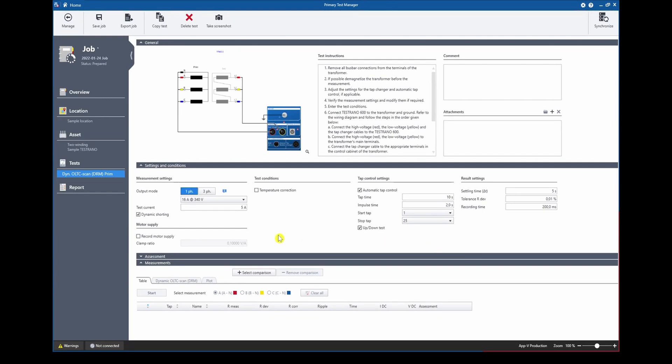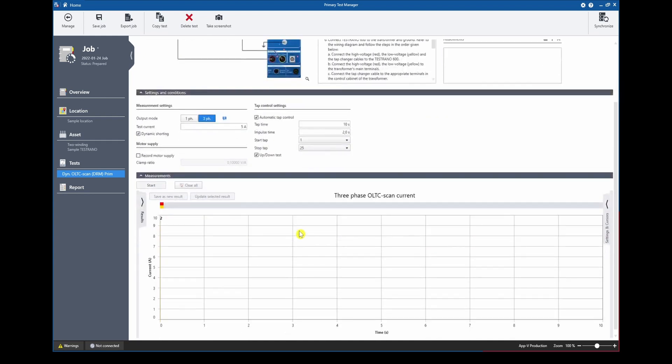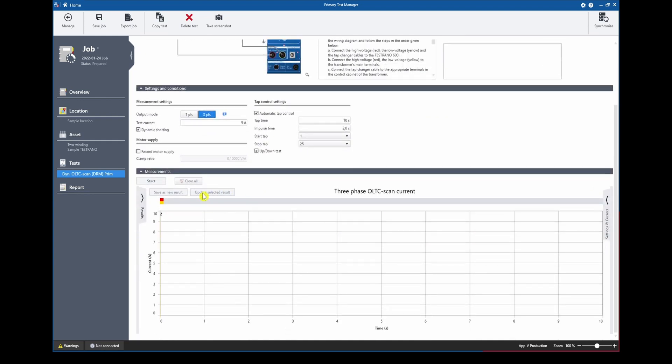Inside the test we can now see that in addition to the original single-phase output mode we have now also a three-phase output mode available. So if we activate this we can enter the test current for our test, we can apply dynamic shorting to the opposite side of our OLTC and we can enter the tap control settings to operate on the tap changer. When we press start and the measurement starts to record the current curves we will see the dynamic current curves at the bottom and if we also record the motor supply below here we will see the motor supply current.